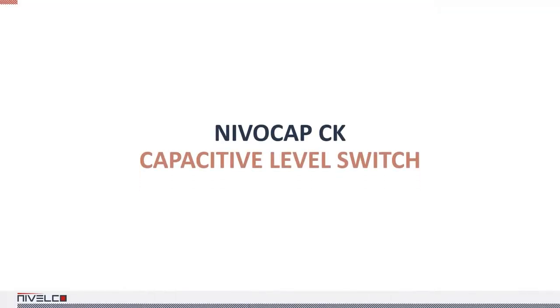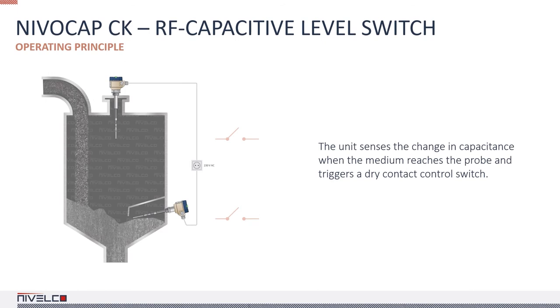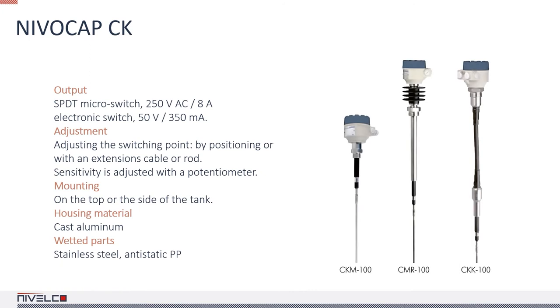The NIVOCAP CK capacitive level switch operates capacitance meters in the radio frequency range, which is less sensitive to material deposits than conventional capacitive devices. The electronics continuously evaluate the voltage level proportional to the capacitance difference between the two probes and the housing. The unit senses the capacitance change when the medium touches the probe and triggers the dry-contact control switch. Using a reference probe enables the device to ignore large deposits on the probes, preventing false switching. The high-temperature and DUSTEX models are suitable for harsh environments, ideal for power generation applications. The units are available only with powder-coated aluminum housing, because one of the measurement reference points is the housing itself.